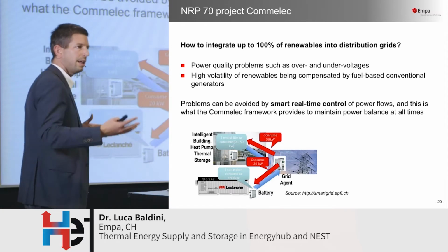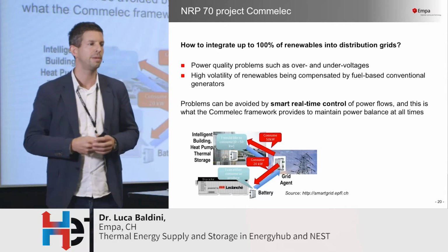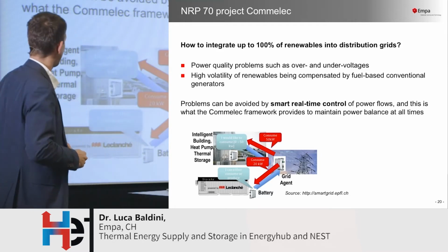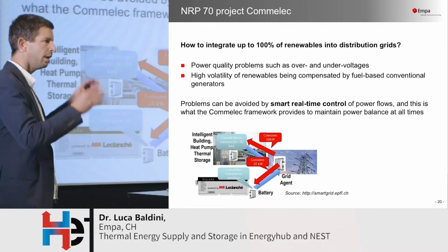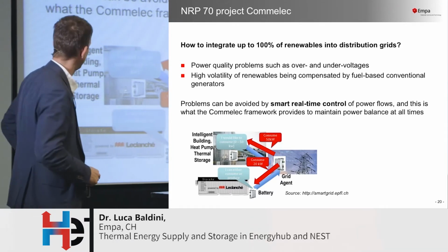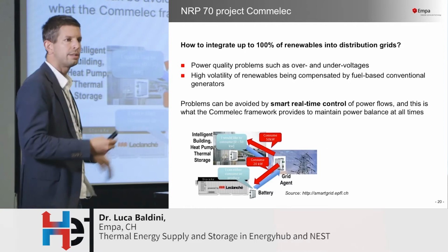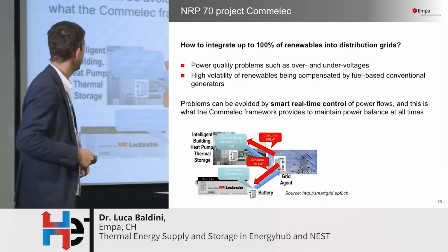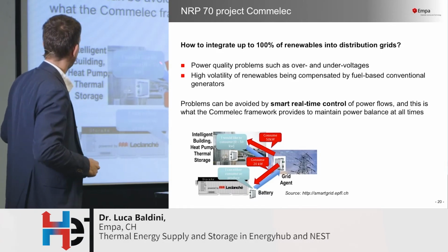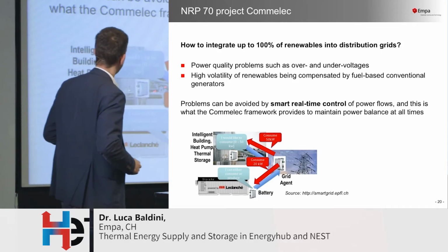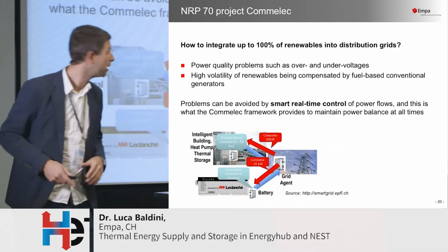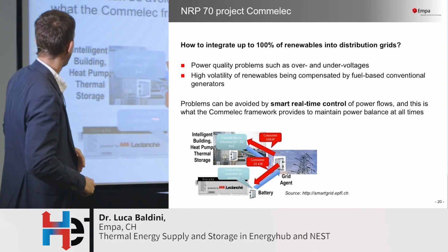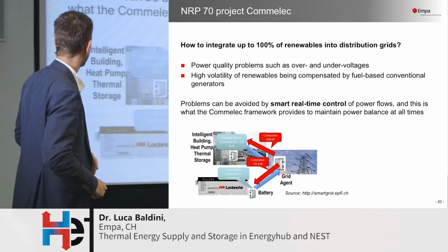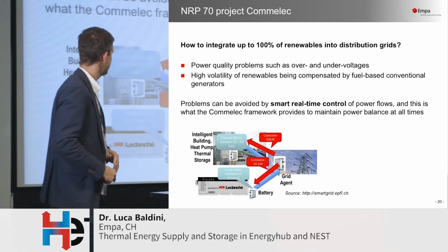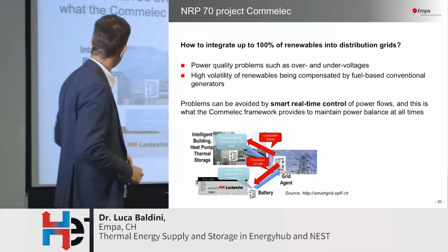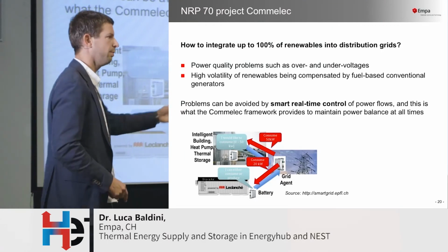The idea is installing a microgrid, implemented at the EMPA campus, where we have a grid agent looking at the status of the electricity grid, and resource agents sitting at the resource or building level, communicating together. Basically, the building control says, I would like to consume 0 to 50 kilowatts in the next hour, the battery pack hooked up to the system says it can consume or produce, and the grid agent says, please consume 50 kilowatts resource agent A, and 20 resource agent B.